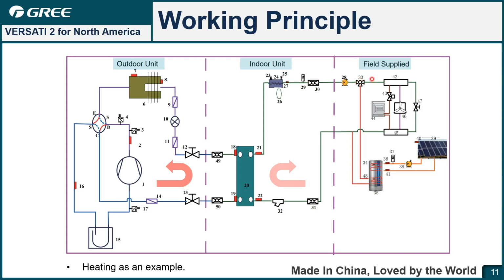For this 3-way valve, you can see it connects with the water tank to supply the hot water to the tank and back, and the other way is circulating to the indoor side, such as the floor heating FCU, and then flow back to the water return. Okay, that's the water circulation in the water pipe.